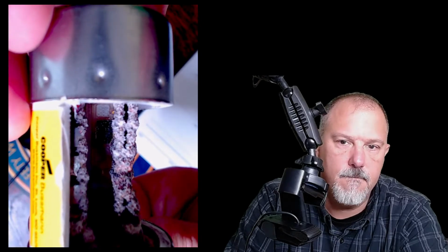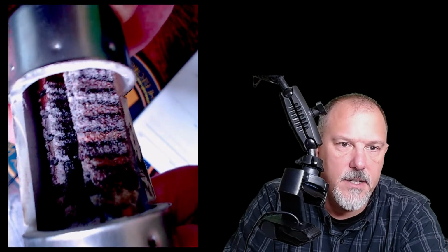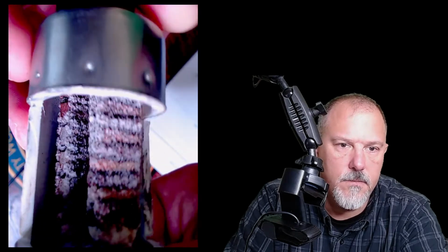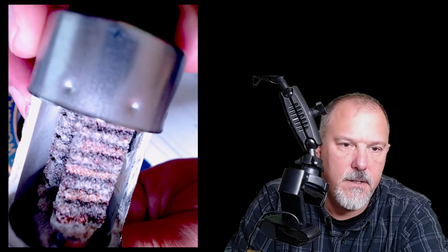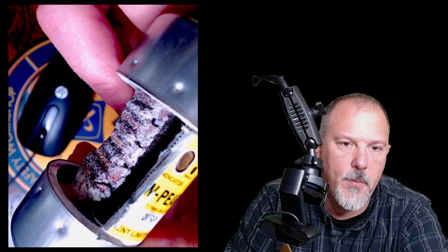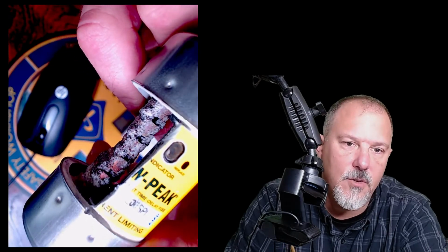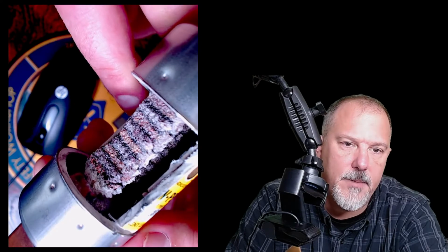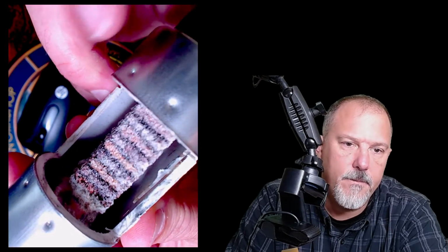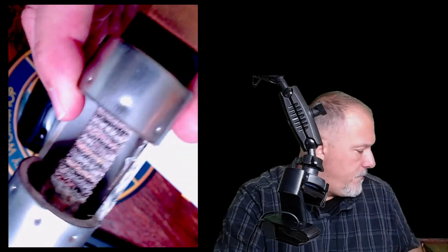That is a spent fuse. You see that? That is what happens inside of a fuse when it is spent. All of those little pinch points are gone. The sand that was in there that is around those elements, that element has vaporized.